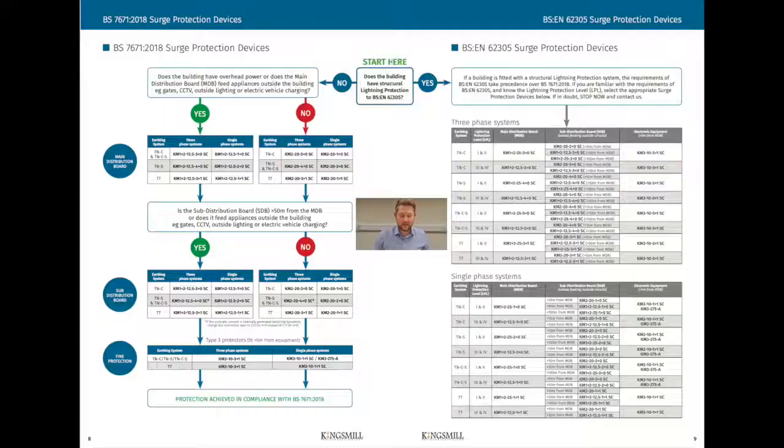We need to know first of all if external lightning protection is installed to the building, and if so, what level of lightning protection is installed. We also need to know what earthing arrangement there is on the building — so TNS, TNCS, or TT — and also if the main supply is either single or three phase. Once we know these pieces of information we can start the process.